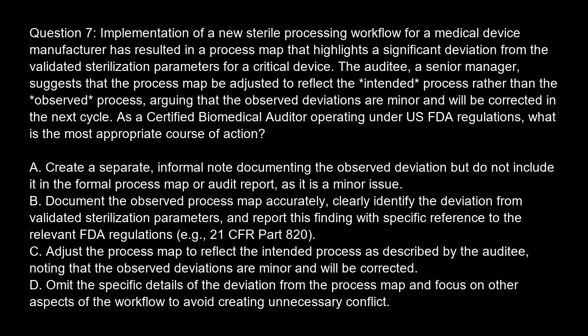Option A. Create a separate, informal note documenting the observed deviation, but do not include it in the formal process map or audit report, as it is a minor issue. Option B. Document the observed process map accurately. Clearly identify the deviation from validated sterilization parameters, and report this finding with specific reference to the relevant FDA regulations, e.g., 21 CFR Part 820. Option C. Adjust the process map to reflect the intended process as described by the auditee, noting that the observed deviations are minor and will be corrected. Option D. Omit the specific details of the deviation from the process map and focus on other aspects of the workflow to avoid creating unnecessary conflict.